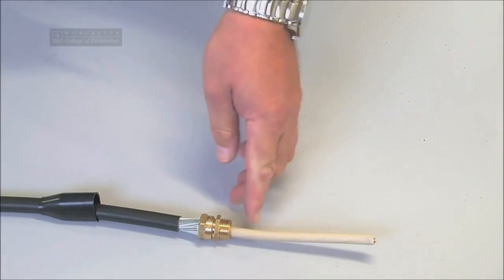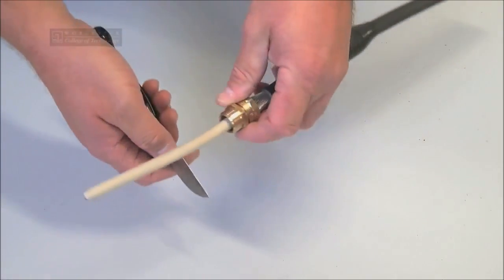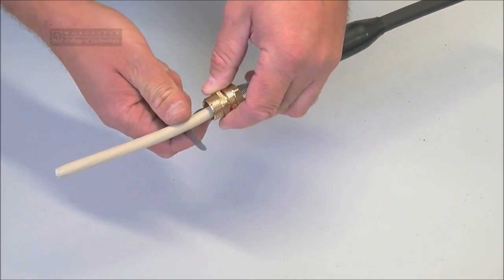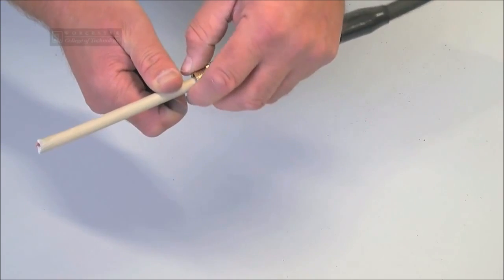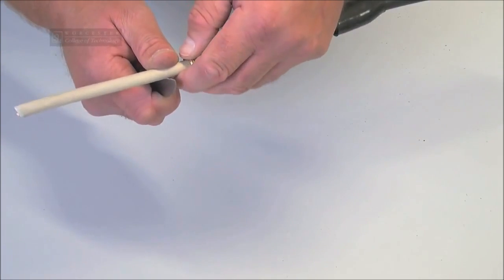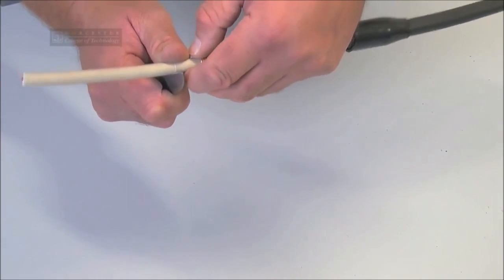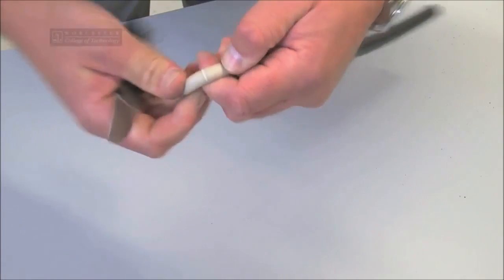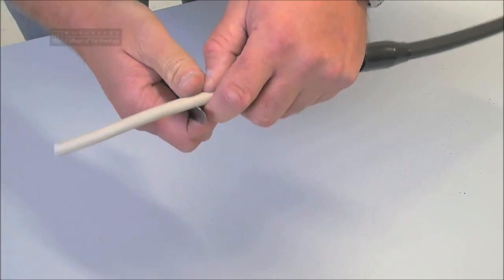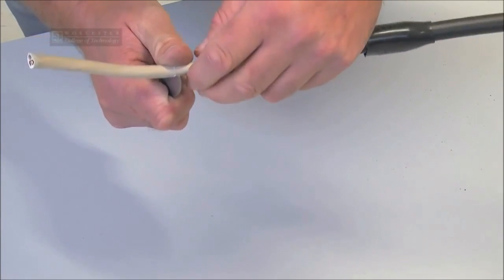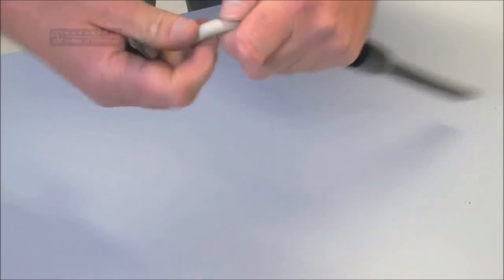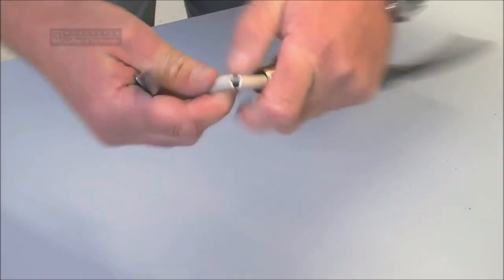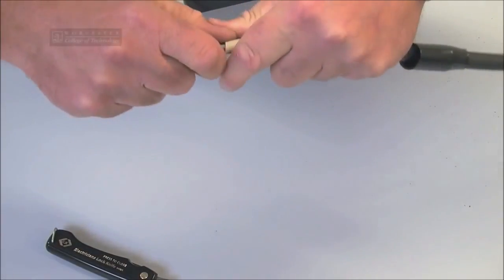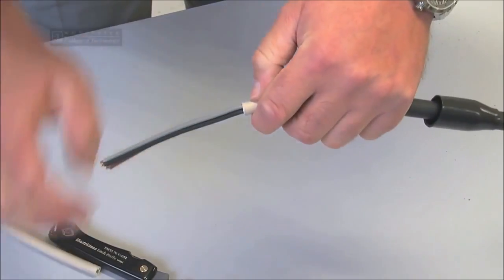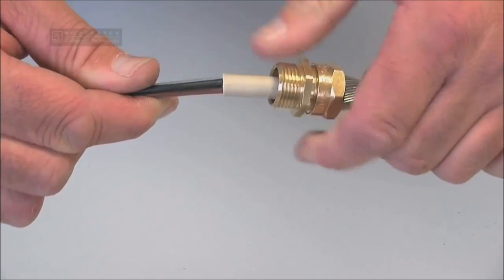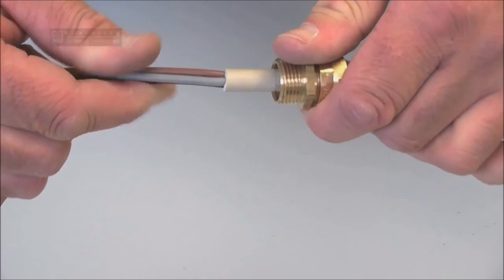We now need to remove the secondary layer of PVC by using an electrician's knife, and again it's approximately 25mm across. We need to be very careful this time when we do score this cable so that we don't go through into the main insulators of the cable. So gently does it. As we go along, we can open to ensure that we don't score the main conductors. Simply pull the insulation off, and as you see, the cables are now ready for termination.